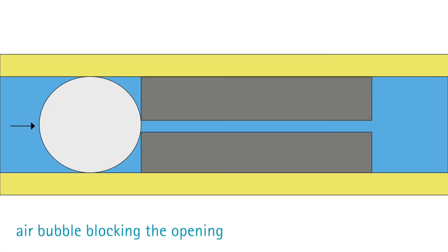Due to the restrictor, the diameter of the fluidic line changes from wide to small and back to wide again, which could cause difficulties when priming the system because air bubbles may block the small opening of the restrictor.